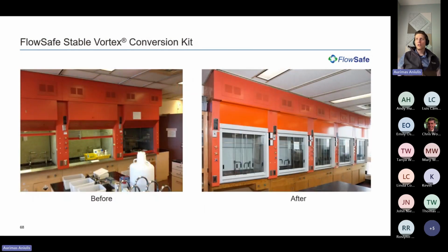Now, one thing also to consider is that sometimes replacing fume hoods is a costly project. A fume hood is a metal superstructure, a metal frame that's typically attached to the walls or to the fume hoods next to it, and sits on top of cabinetry and work surfaces. So what we also offer is a conversion kit where you can keep all your sheet metal in place, and just the internal baffles and the geometry of the sash need to be replaced. In this specific project, they had asbestos in the walls, and if they were to pull out this fume hood, they would have to do asbestos remediation, which was a showstopper for them from a financial standpoint. So a conversion kit became a very appealing solution, where they could retrofit 50 fume hoods without having to do asbestos remediation because they never cut into the walls.